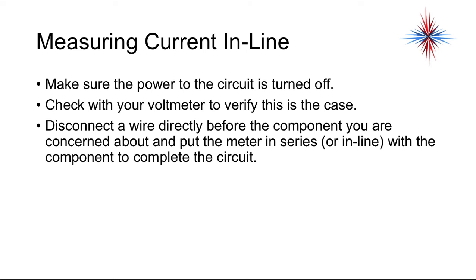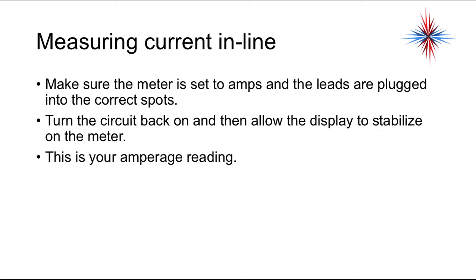Disconnect a wire directly before the component you're concerned about and put the meter in series or in line with that component to complete the circuit. Make sure the meter is set to amps and the leads are plugged in to the correct spots. Turn the breaker back on and allow the display to stabilize on the meter. This is your amperage reading.